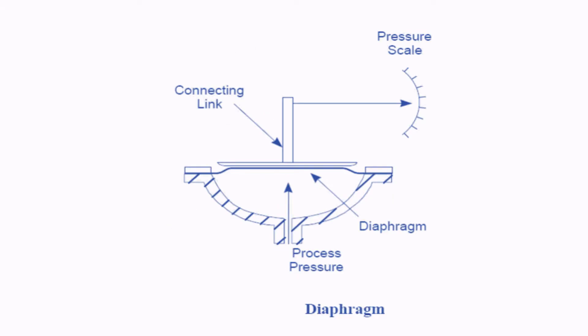Finally we have diaphragm gauges. A diaphragm is essentially a flexible disc that changes shape when the pressure changes. You can see here that the center part of the diaphragm is exerted upon by the pressure, and it moves such that it moves a connecting link, which is connected to a pointer that moves on the dial scale. This is how a diaphragm gauge works, and these are the three different types of deformation gauges.